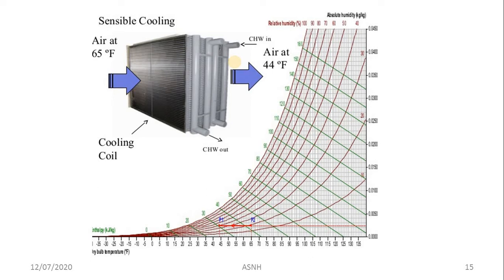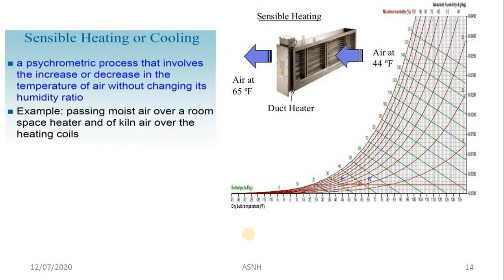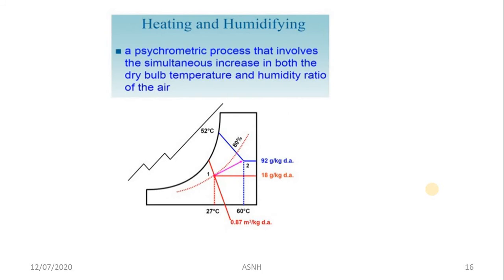Sensible cooling means reducing or lowering the temperature without changing the humidity ratio. Heated air is passed through cooling coils to obtain low-temperature air. On the psychrometric chart, the x-axis shows dry bulb temperature and the y-axis shows humidity ratio. Cooling is shown as a horizontal line with the arrow pointing left, and heating points right — both at constant humidity ratio.